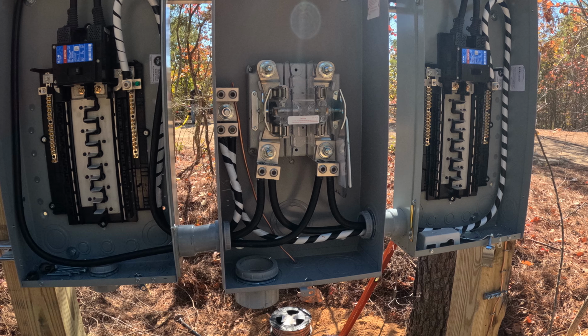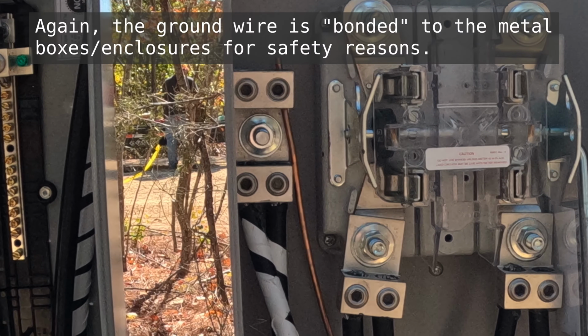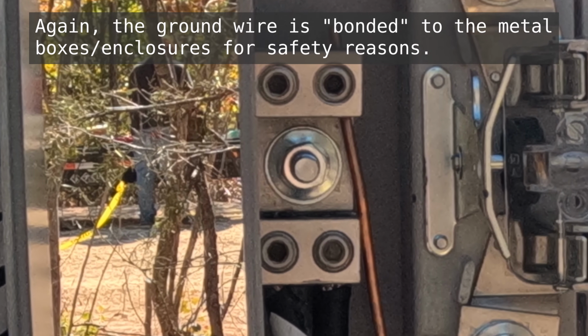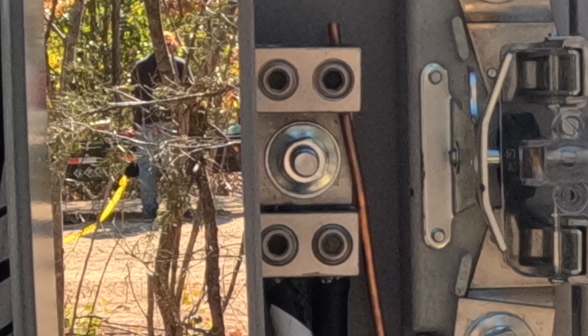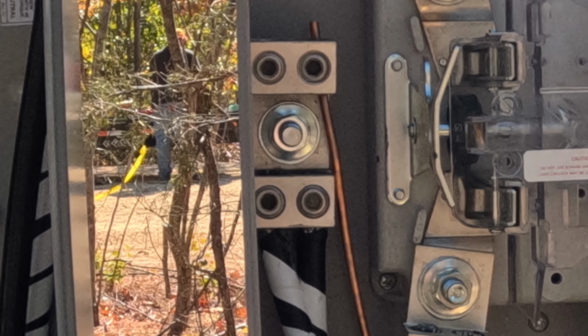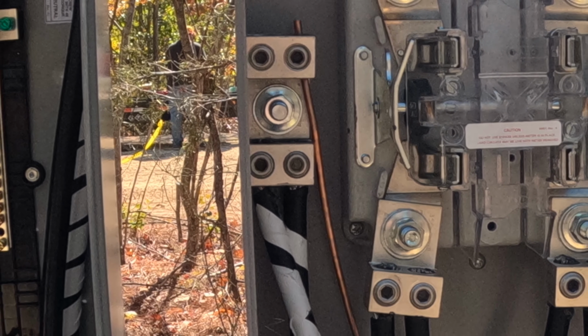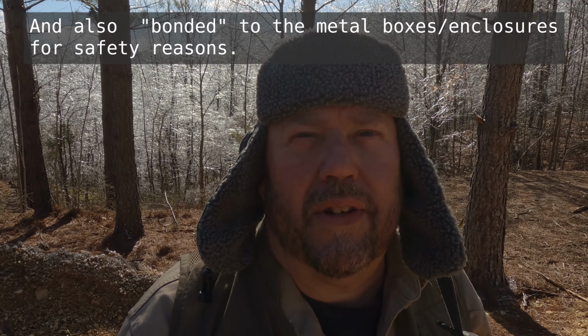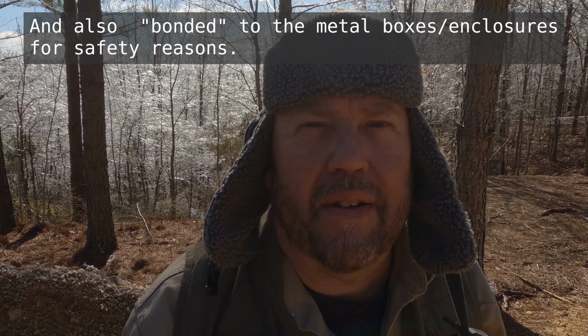You may hear the term bonding or bonded. That means the neutral wire from the service and the ground wire that goes into the ground are bonded, or connected, together, and that's done at the meter base. As you can see in the videos, the ground wire and the white wire with tape around it go to the same block. That's called bonding, the ground is bonded to the neutral. I just wanted to make clear what the word bond or bonding means.